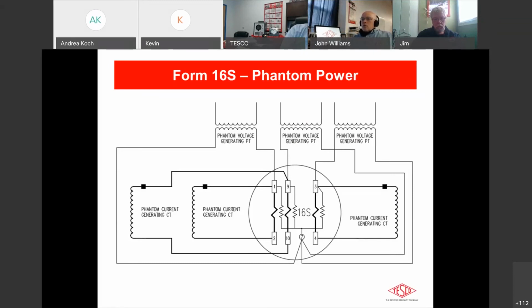So, as I mentioned before, in terms of generation of the voltage and the current in the test boards, those 2 channels, the voltage and the current, are typically low power outputs: high voltage, low current, and high current, low voltage. So one might run into a problem with activating these disconnects if they're consuming 750 up to almost 1,000 VA inrush to pull in some of these disconnects.